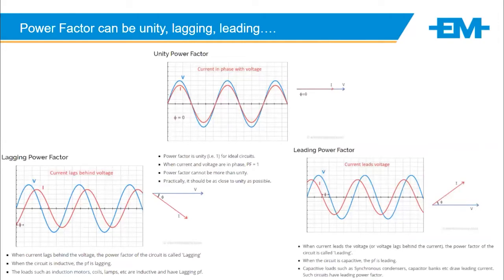Now, what you would see, so power factor can be in three different segments. Unity power factor is what we call an ideal circuit. If a circuit was purely resistive, voltage and current would flow in unity, and that's what we refer to as unity power factor. So if I took kilowatt over kVA, that would be equal to 1. So they're in unity. Typically, if you've got a lot of motors and you've got no correction on those motors, you would start getting what we call a lagging power factor. That is when the current is lagging behind the voltage. All right. And this is an inductive load. Okay. This is what we try and fix with power factor correction.